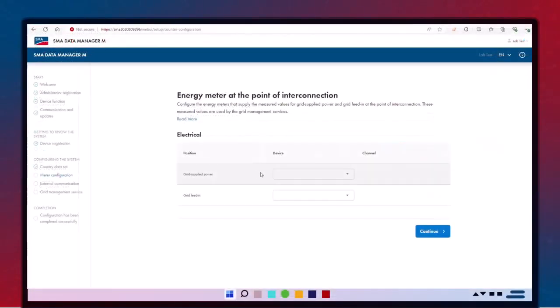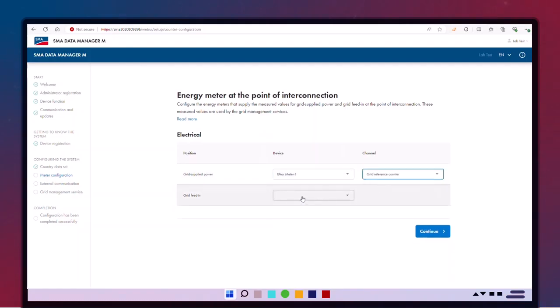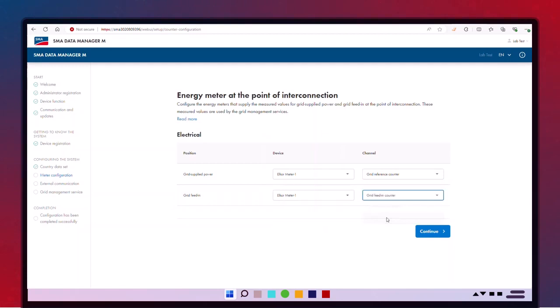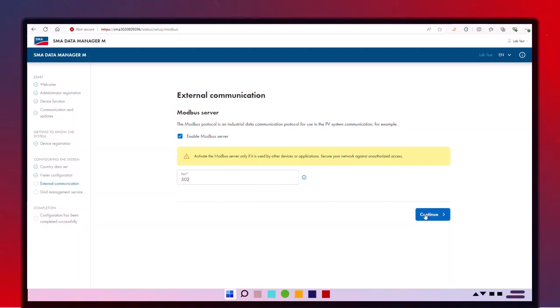If an energy meter was added in the previous Finding Devices section, specify here which meter is at the point of interconnection. Then, configure the grid reference and feed-in channel accordingly. Enable Modbus Server if the Data Manager will be communicating with the SCADA system.